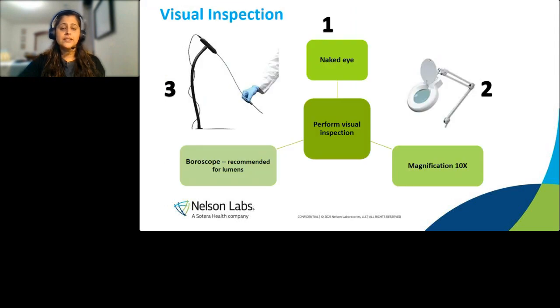Visual inspection, as it's done in the healthcare facility, we also do through the naked eye. Just looking at it, that's our first. Second is under magnification. This is for complicated devices or duodenoscopes that we're validating, to see the distal end portion of it. Borescope upon request only. We don't do it for everything because it's not required. If the manufacturers specify that they want us to go in and look, then we would do it. But otherwise, one and two are what we would use.